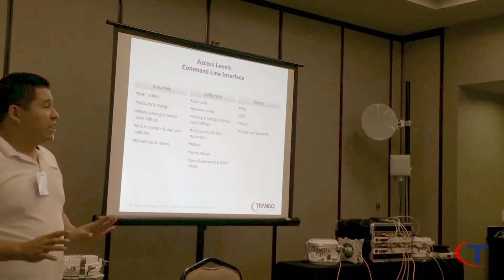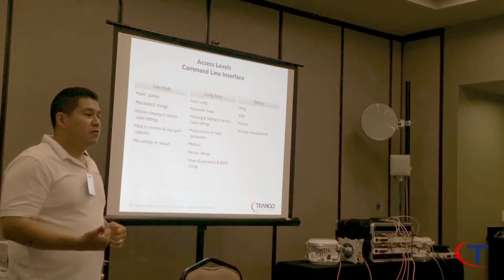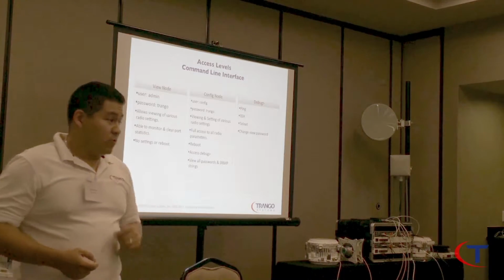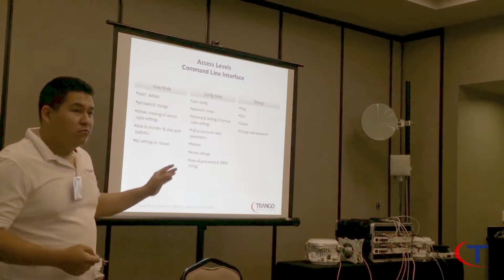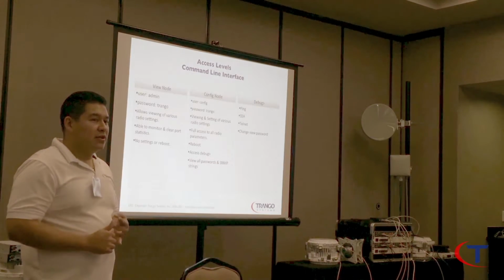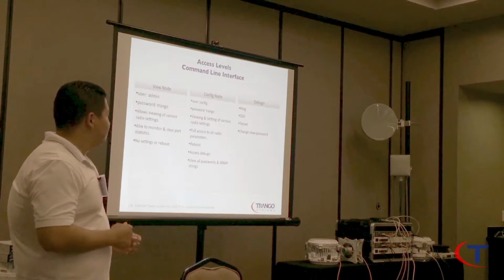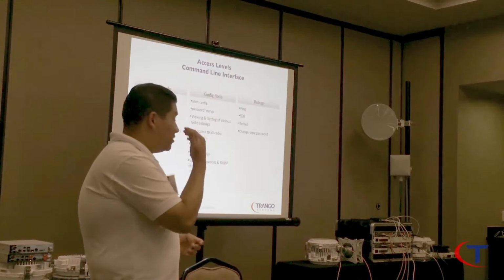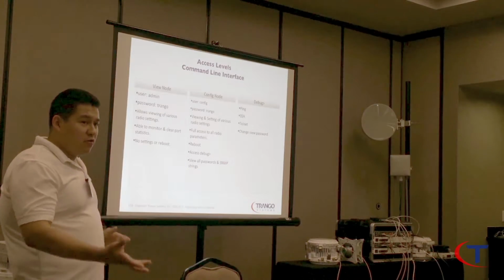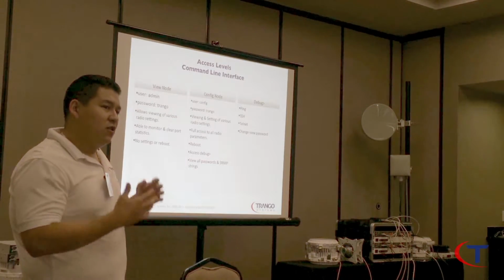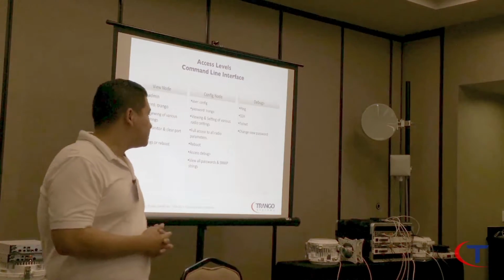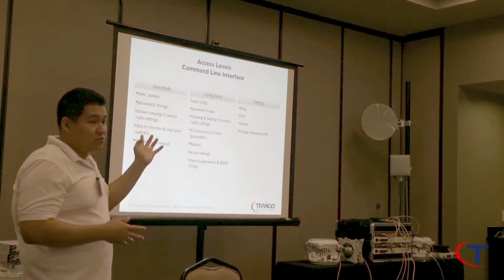The features don't change. From the view mode, you can go in there, check parameters, clear the counters, but you cannot reboot the radio. From the config mode, now you can change parameters, change IPs, whatever you want, and reboot the radio. So you have the power. From the debug prompt, we can actually jump interfaces, go to another radio, another device on the network. As long as it accepts a telnet or SSH session, I can connect to it. And change the view password as well.